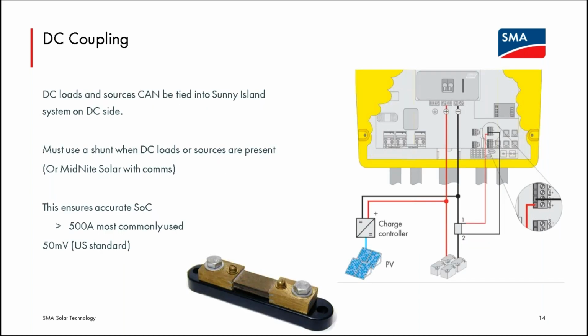If someone has an older PV system with the Sunny Island, and they had a PV system and a charge controller, we don't want to force them to have to buy a new inverter. They can couple that into the DC side of the Sunny Island. The charge controller output would have to be 48 volts for that to be compatible.